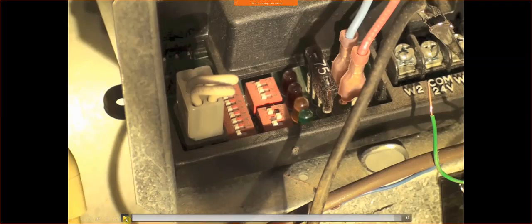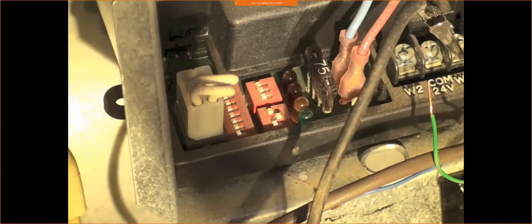All right, so the guy showed different codes for different things. He mentioned a couple things I want to talk about too, so you guys just know the terminology. First is the soft lockout and the hard lockout. So when a system starts for the first time, it may encounter an issue. By design, let's just say the flame doesn't kick on for the first time. It could be many reasons. Maybe the gas was off, or you bumped something, whatever the case may be.